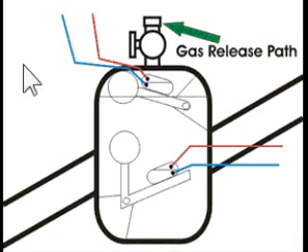By collecting the accumulated gases from the gas release pockets on top of the relay and by analyzing them one can predict the type of fault in the transformer.